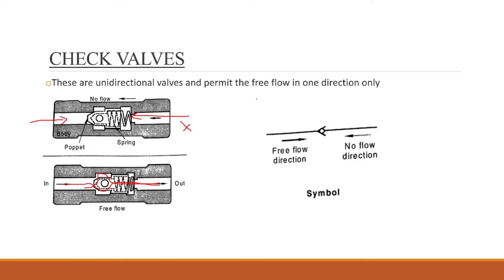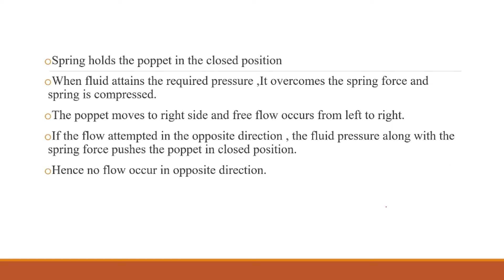The check valve is represented by a symbol in the circuit diagram. The symbol shows that flow is allowed in one direction but blocked in the opposite direction. The spring holds the poppet in the closed position. When incoming pressure overcomes the spring force, the spring is compressed and the poppet opens.